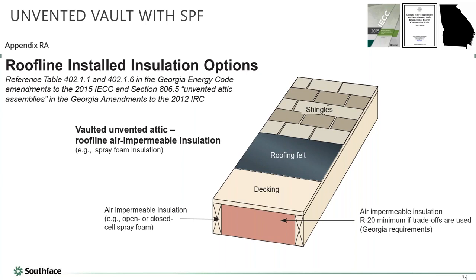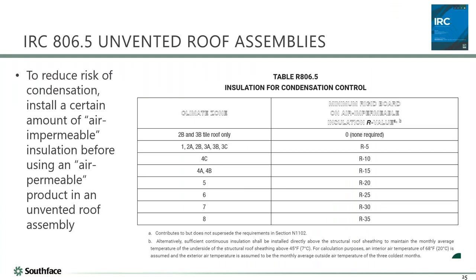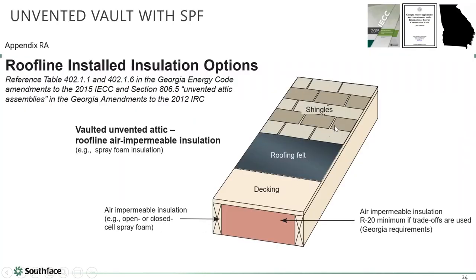The newer approach is to use spray polyurethane foam applied directly against the underside of the roof deck — the code allows this. In Georgia we have a backstop table with a minimum: you don't have to do the full R-38, but you must do at least R-20. That can be either open or closed cell foam.